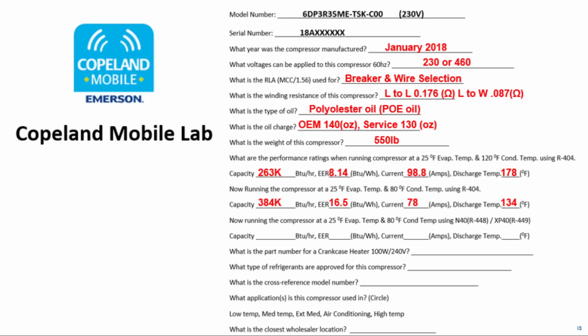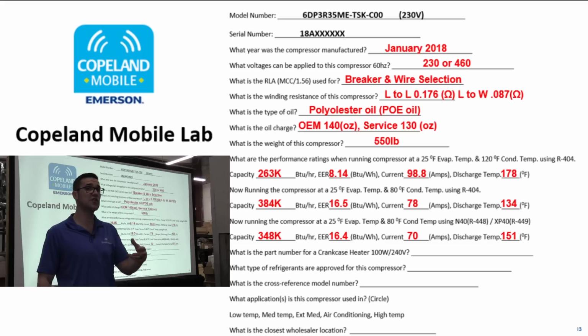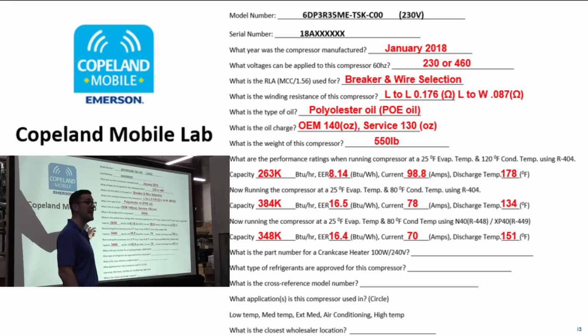80 and 125 and 80. So look at the capacity difference in the same compressor with a different refrigerant, just to show you if you're using different refrigerants, you're going to have different capacities. And look at the discharge temperature. Very important to understand that stuff, because when you're doing a refrigerant retrofit, this is something that you really need to think about. I've seen it where contractors weren't meeting capacity because they did that refrigerant change. So you got to think about that stuff.